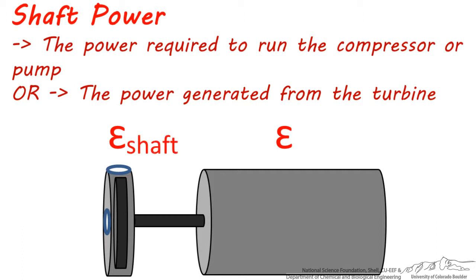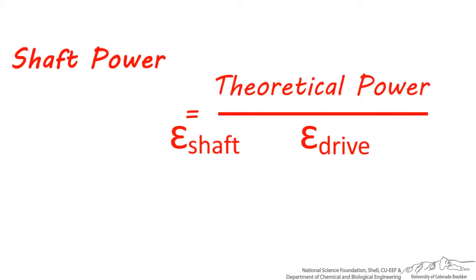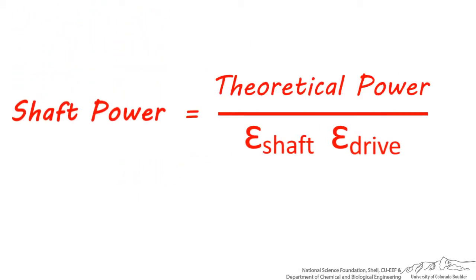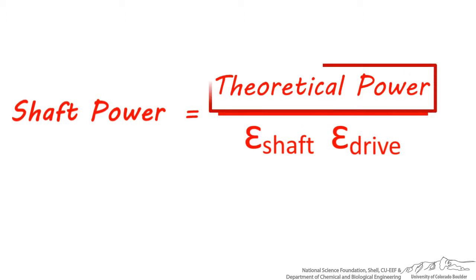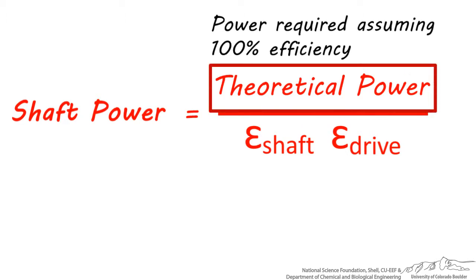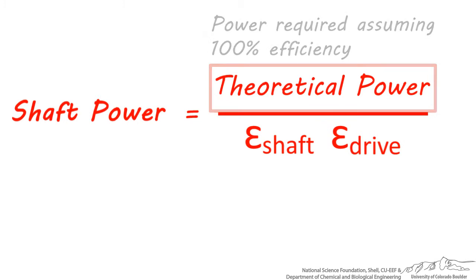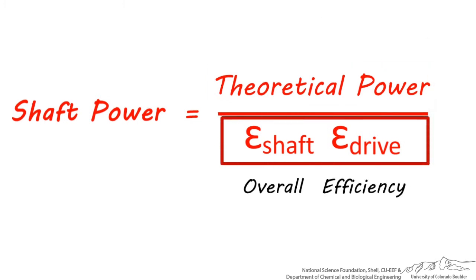The compressor or pump has a shaft efficiency, and the motor has a drive efficiency. These are both important in calculating the shaft power, which is the theoretical power divided by the shaft efficiency times the drive efficiency. The theoretical power is the power required to run this piece of equipment assuming both the pump or compressor and the drive are 100% efficient. This combination of shaft and drive efficiency is considered the overall efficiency for the piece of equipment.